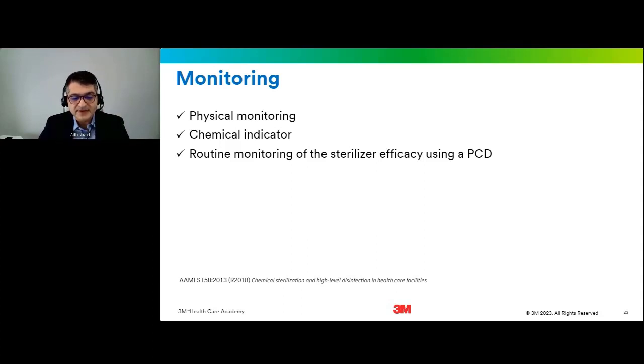Based on ST58, an internal chemical indicator should be used inside each package, each tray, each containment device, rigid sterilization containment system, instrument case, cassette, or organizing tray that is going to be sterilized. The chemical indicator should be placed in the area of the package, tray, or containment device that creates the greatest challenge to sterilant penetration. You may consult the manufacturer's instructions for use for this part.